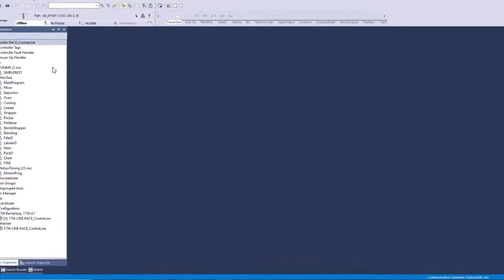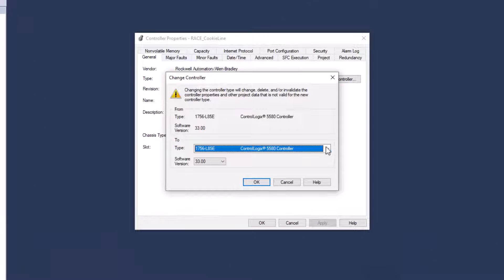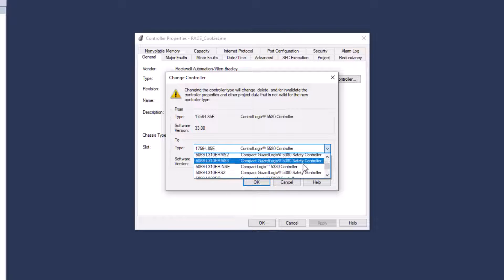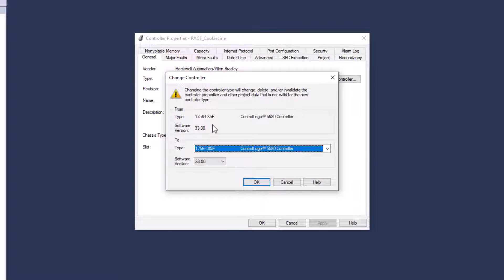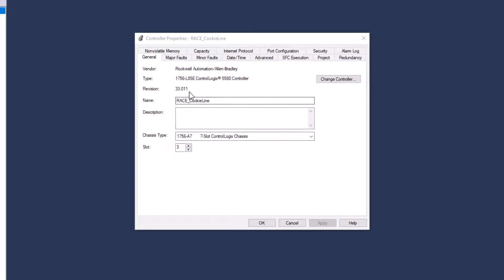Let me show you what's going to happen though. When you go to change your processor type, you're not going to be able to change that to an emulator - they just don't allow that. This version is running an L8 processor - specifically an L85E. You can go in there and use the L5K format to change that to a different processor type. But when you get up to version 36, you will no longer be able to do that anyway because they changed the instruction types. Just keep that in mind.